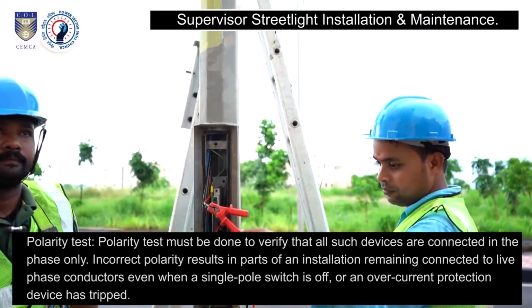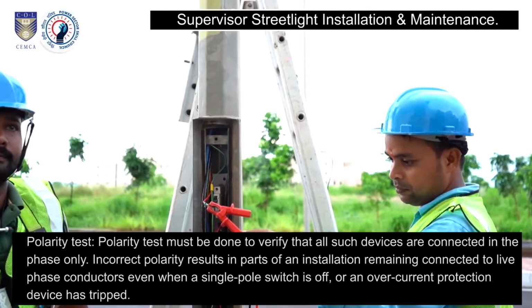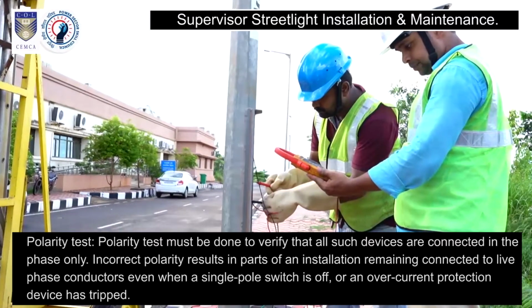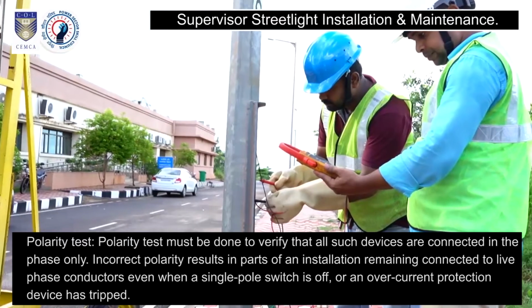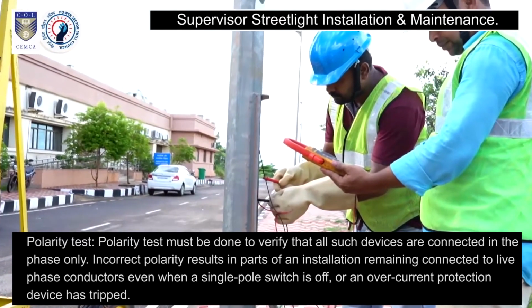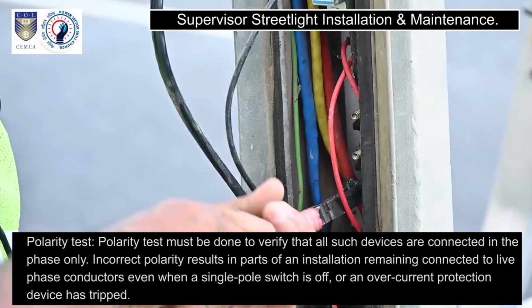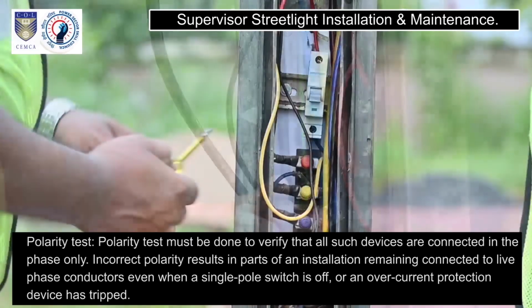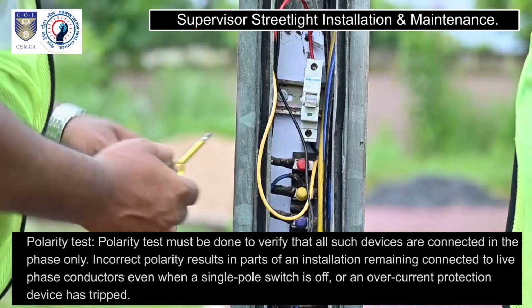Polarity test. Polarity test must be done to verify that all such devices are connected in the phase only. Incorrect polarity results in parts of an installation remaining connected to live phase conductors, even when a single pole switch is off or an overcurrent protection device has tripped.